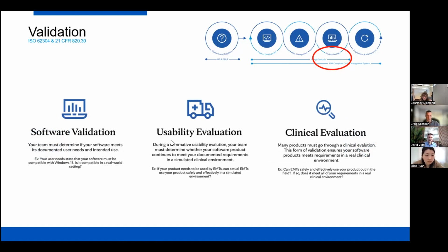So typically these would all be lumped together into one protocol. But the validation will include software validation, right? Making sure it actually functionally works in its intended setting the way it's supposed to work. Usability evaluation to ensure that those who are actually intending to use the product understand it, right? Like can actually guide their way through it and make sure that they get the right results. And then clinical evaluation, which might be sensitivity, specificity, or some identification of whether it's actually aligned to the clinical standards.